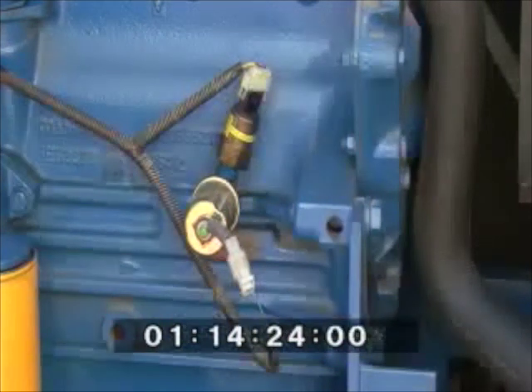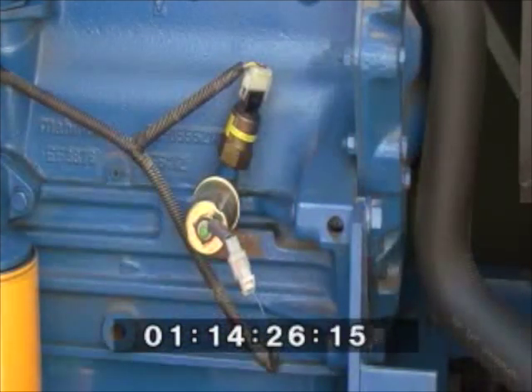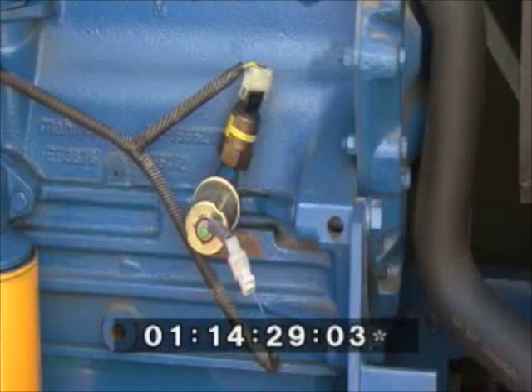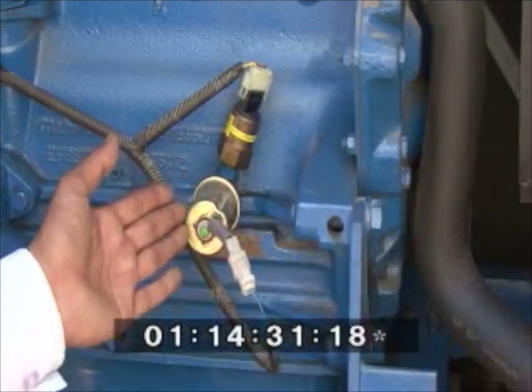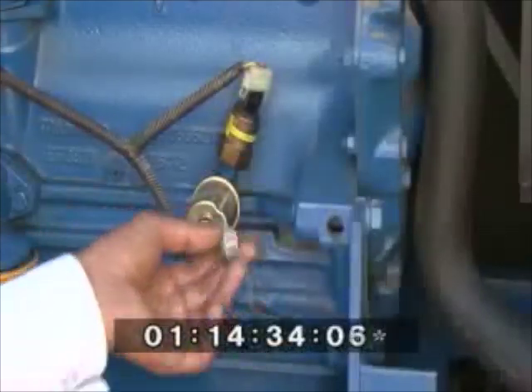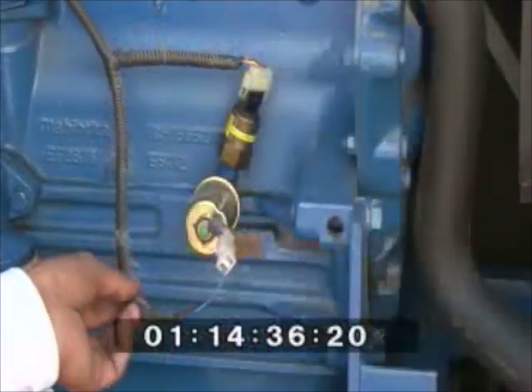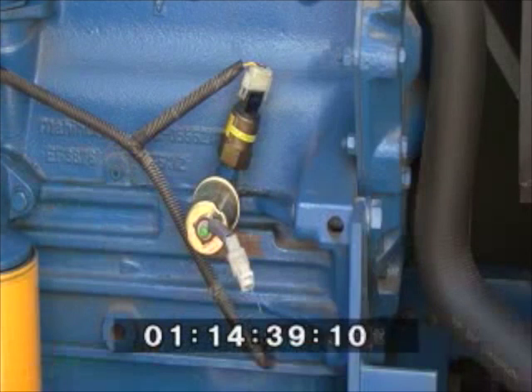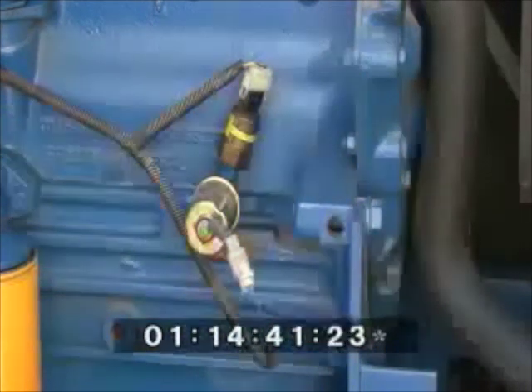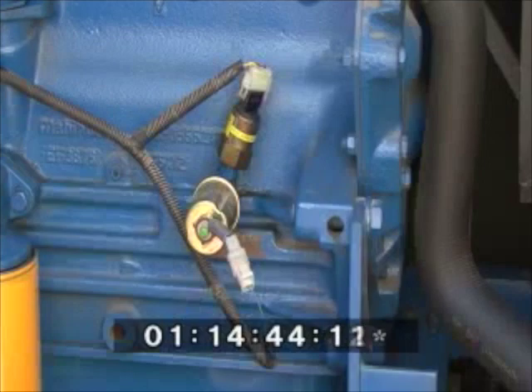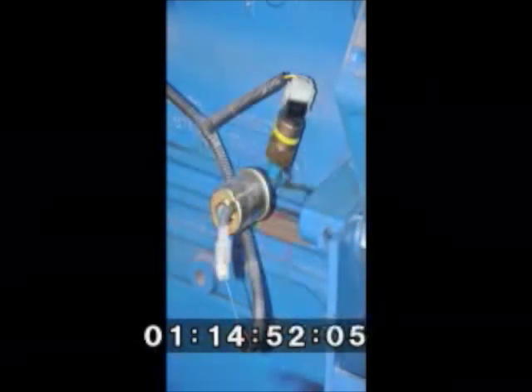Now we will see the system of checking the lubricant oil pressure. You can see the LLOP now, which stands for low lube oil pressure. The wire attached to it generates an alarm in case the lube pressure is low. The alarm can be viewed in the door panel as well as the alarm multiplexer.